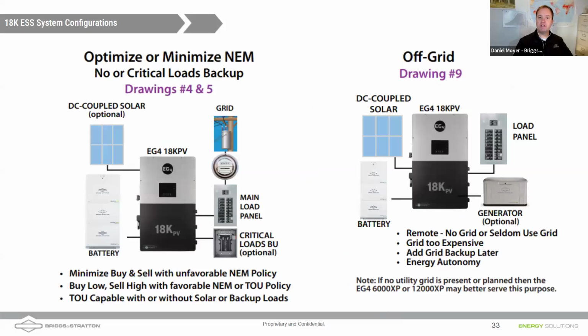Well, let's jump into some of those single line diagrams. So we're going to start with the 18kPV. On the left there, we've got our grid, our meter socket, and our main load center, flowing into the grid port on the 18kPV. Coming out of the 18kPV, we're going to our critical loads backed up panel.